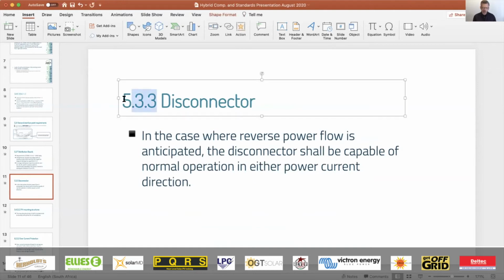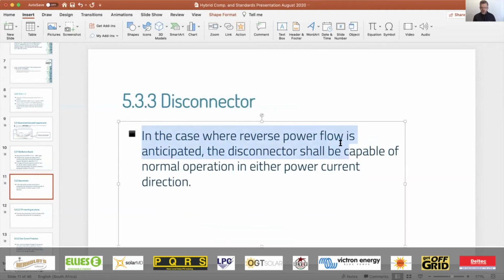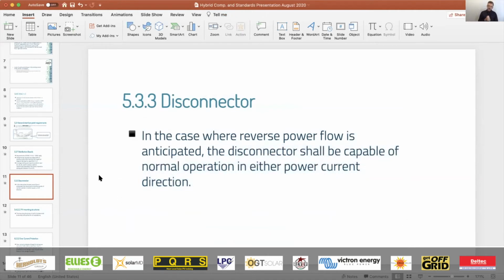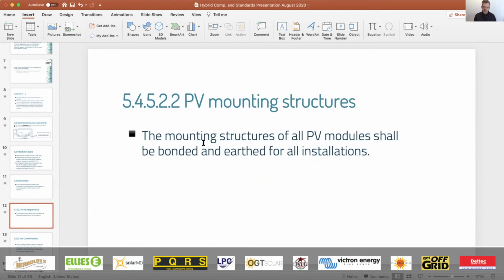Disconnectors. So up on the title of the slide, you see the reference of where it sits in the standard, and that reference talks about disconnectors. And over here it says, in the case where reverse power flow is anticipated, the disconnector shall be capable of normal operation in either power current direction. Now, I've got a lot of guys asking questions about DC disconnects, but they don't ever say, can this disconnect handle a reverse current flow? And I thought of including this just to raise a bit of awareness around the fact that if you are going to be fitting disconnectors, you've got to make sure that they can handle reverse power flow.